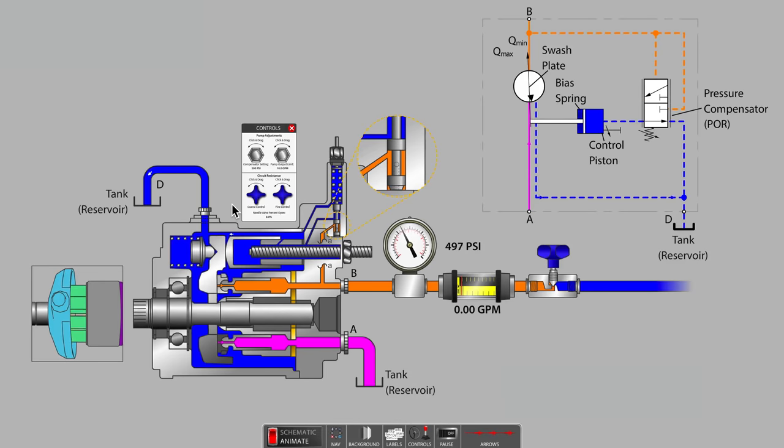If the hydraulic system requires a top system pressure of say 1,000 psi, we will need to adjust the pressure compensator spring. This adjustment needs to be made when there is no flow possible on the pump's outlet. In many systems, it simply requires one to stop operating the directional valves.